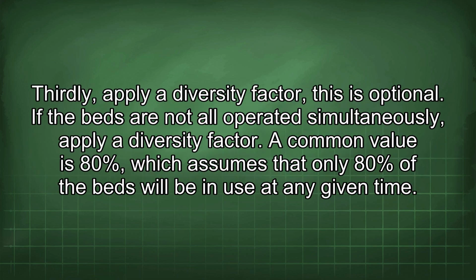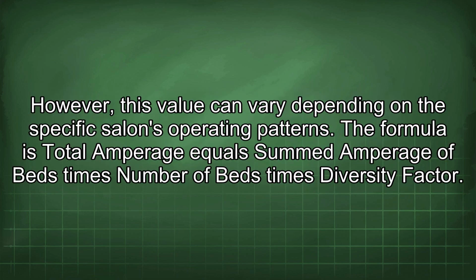Thirdly, apply a diversity factor. This is optional. If the beds are not all operated simultaneously, apply a diversity factor. A common value is 80%, which assumes that only 80% of the beds will be in use at any given time. However, this value can vary depending on the specific salon's operating patterns. The formula is total amperage equals amperage of each bed times number of beds times diversity factor.